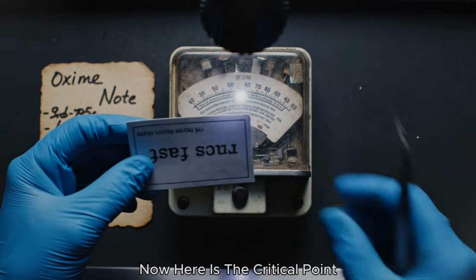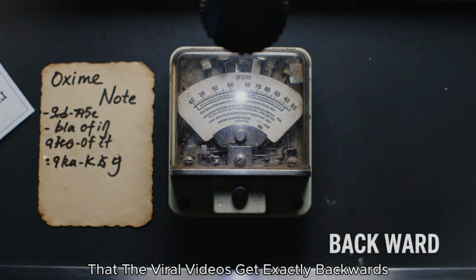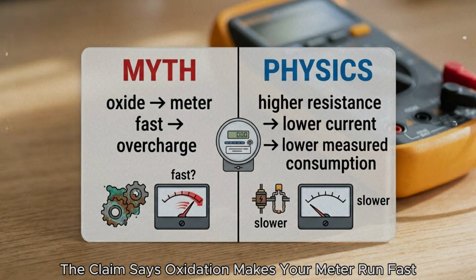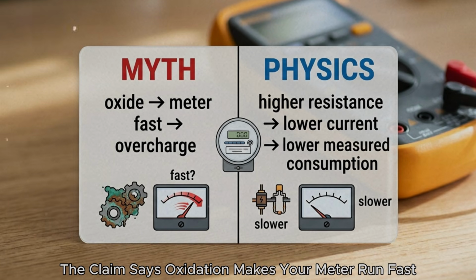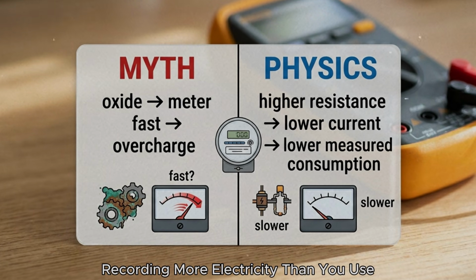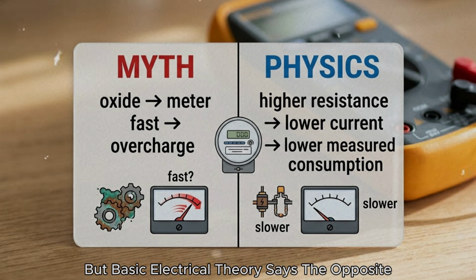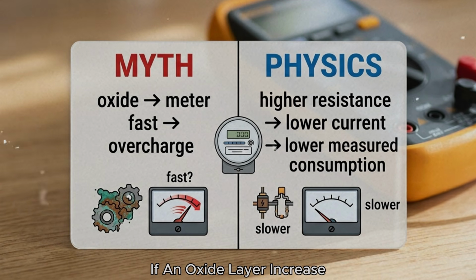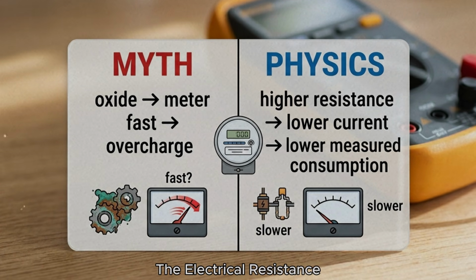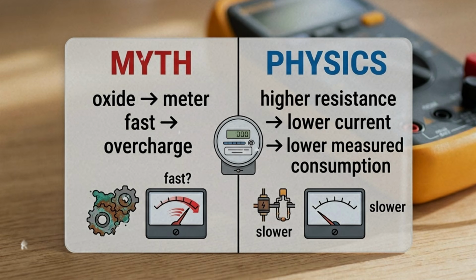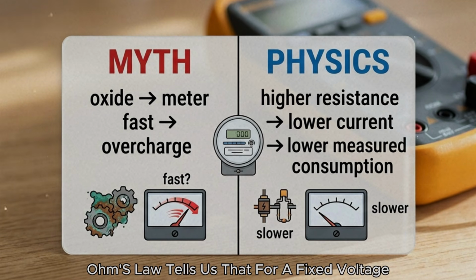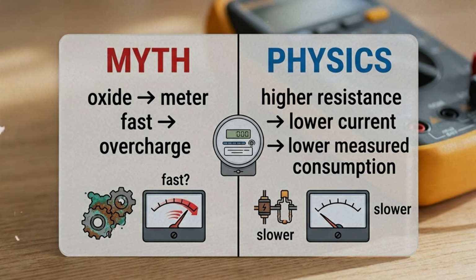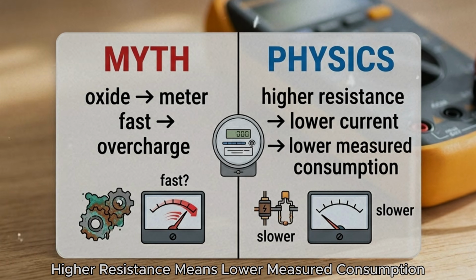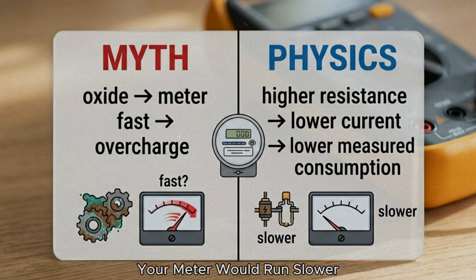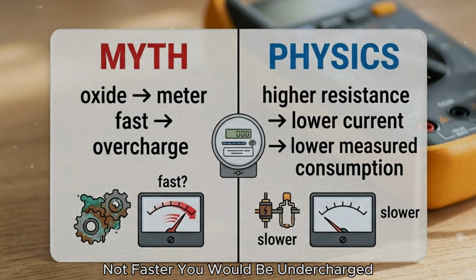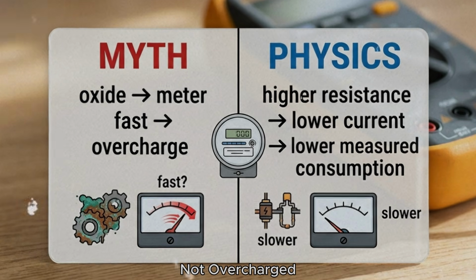Now here is the critical point that the viral videos get exactly backwards. The claim says oxidation makes your meter run fast, recording more electricity than you use. But basic electrical theory says the opposite. If an oxide layer increased the electrical resistance within the meter's internal connections, Ohm's law tells us that for a fixed voltage, current decreases. Higher resistance means lower measured consumption. Your meter would run slower, not faster. You would be undercharged, not overcharged.